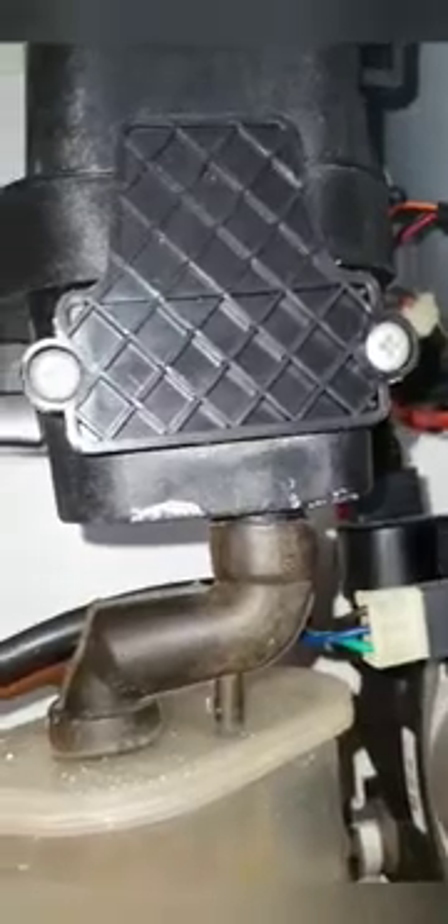Having done the initial safety checks, isolate the gas and the electricity. I'm going to take off the inspection cover on the front of the sump. This is usually where it leaks from, just above where those screws are. Lift off this turret and swing it to the left and pull it down and away.